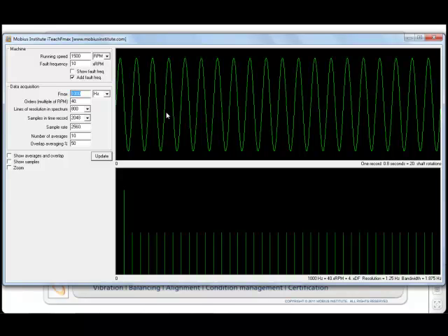The other important thing, going back to your spectrum, is that we're trying to get repeatability. We want the machine to go through enough rotations and for enough time to pass so that all the noise and the process noise and the gears turning and the bearings rolling and all those things all have enough time to occur such that if we were to repeat the measurement, we would get the same measurement. If you cut back too much on your measurement specs, then yep, you'll save some time at the machine, but your measurements will not be repeatable. That means that if you were to test the machine again, the spectrum could look quite different.